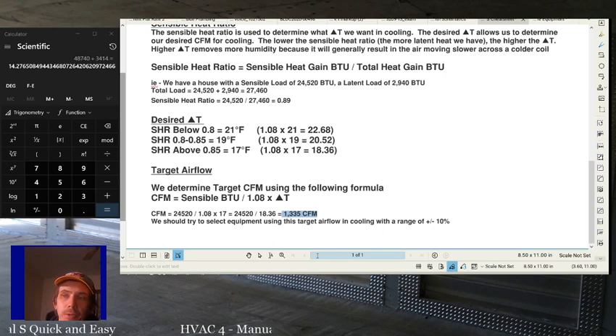It's a lot, right? That's a pretty big CFM number. We should try and select equipment using this target airflow in cooling with a range of plus or minus 10%. So a lot of times you're not going to find published data for 1,335 CFM, but you pick the published data that's as close as possible to this number while trying to be within plus or minus 10% of it. And that's how you determine how much CFM you need. So this right here should already tell you we're probably in the 3-ton range. We need under 30,000 BTUs, but we're in the 3-ton range on equipment.